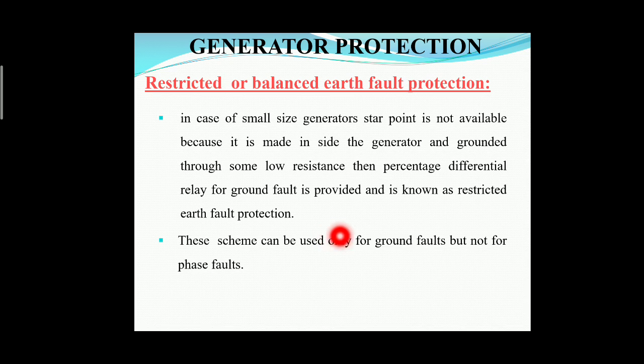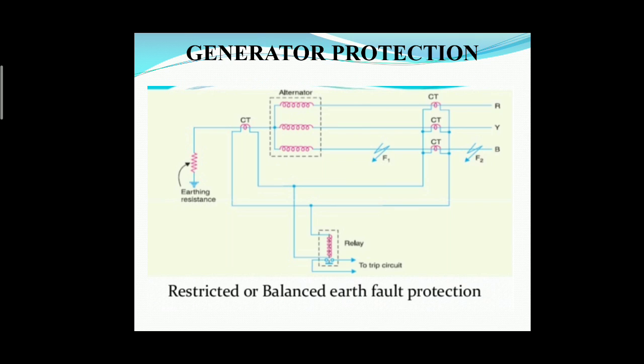This scheme can be used for the ground faults, but not for the phase faults. This is the restricted or balanced earth fault protection. This is the schematic diagram for the restricted or balanced earth fault protection.